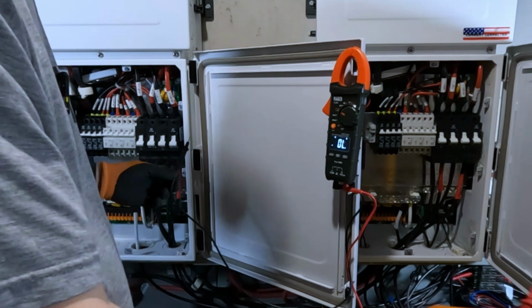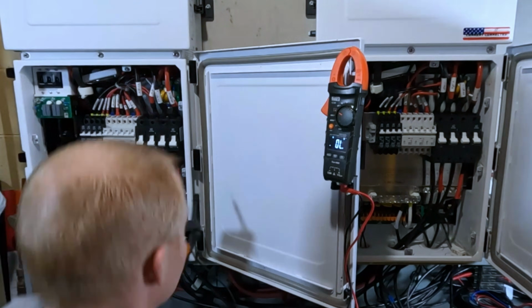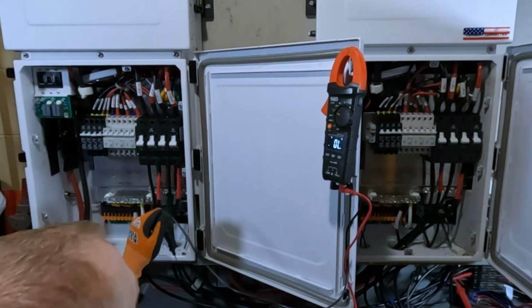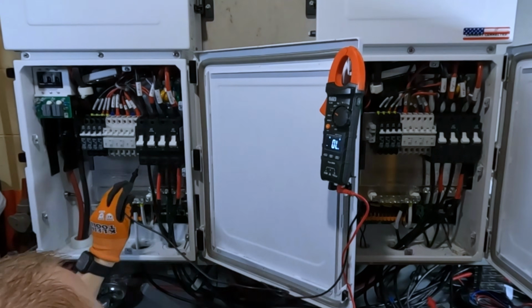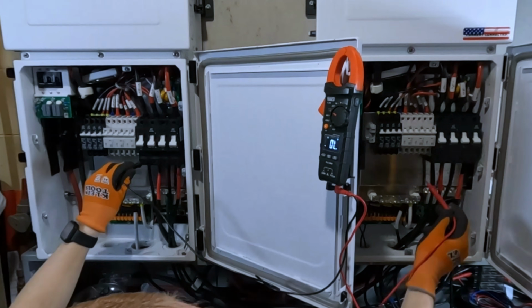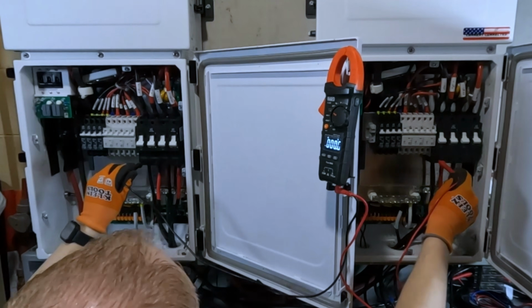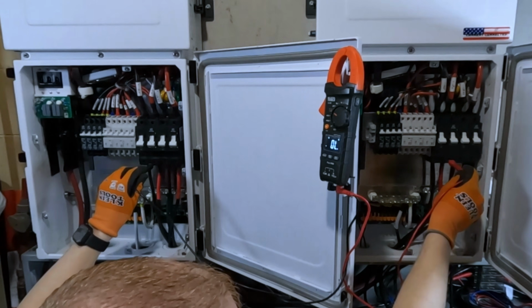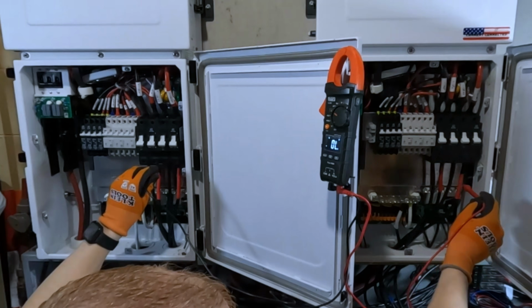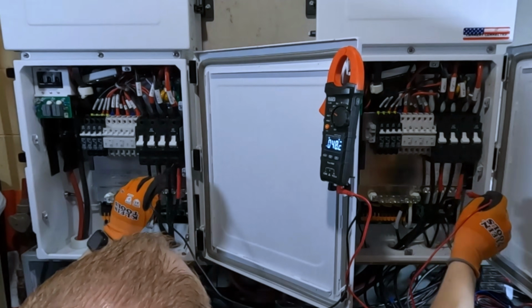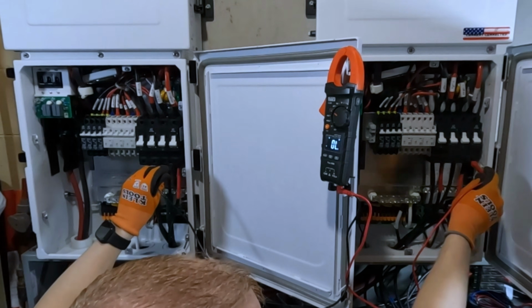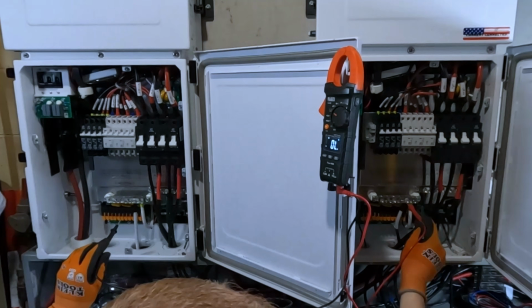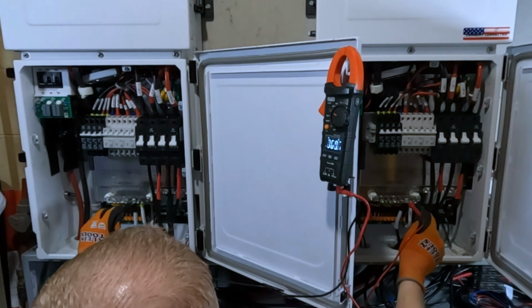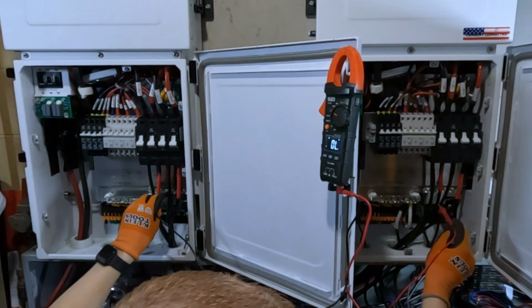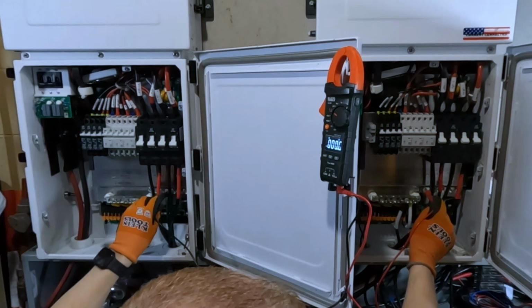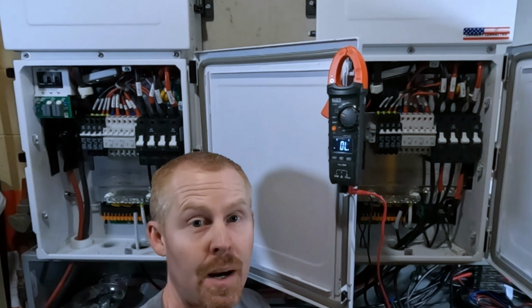So let's see if that stays. We're going to check and make sure that circuits are connected together. So L1 output, L1 output. L2 output, L2 output. L1 input, L1 input. L2 input, L2 input. Come down to our neutral bars. Good. Our ground bars. We've got things wired up properly.